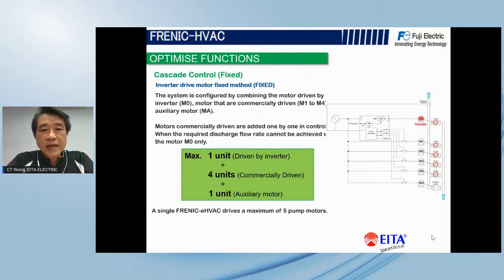Okay, you can see that all this control, just now, you need a pump controller to do that. But today, the inverter is getting much smarter. You can basically skip the pump controllers. As I say, the inverter is able to run independently to control the motor speed and fulfill the pressure demand. Let us go through the cascade control that is already built into the inverters.